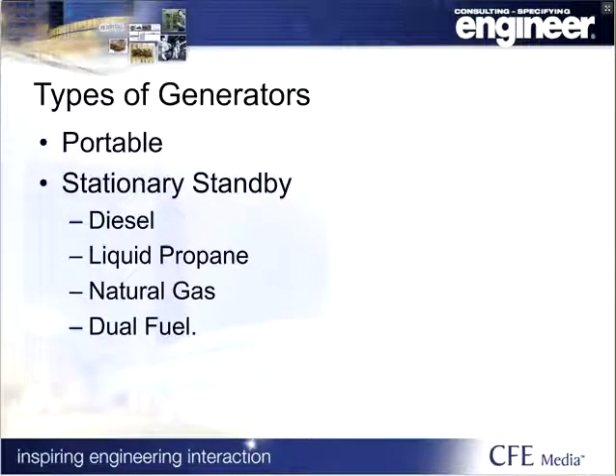Okay, so when designing your generator system, there are several options depending on the project size and needs. Small facilities where the emergency loads, such as egress lighting and exit signs, can be addressed with fully automatic unit equipment, and fire alarm systems addressed with localized batteries, may opt to install a quick connection unit for a portable generator for extended outages only. Permanently installed stationary standby generators have a few options for fuel sources. Diesel fuel oil is the most prevalent. Liquid propane and natural gas are also options. A dual fuel or bi-fuel system allows the generator to operate on a blend of diesel fuel and either liquid propane or natural gas.